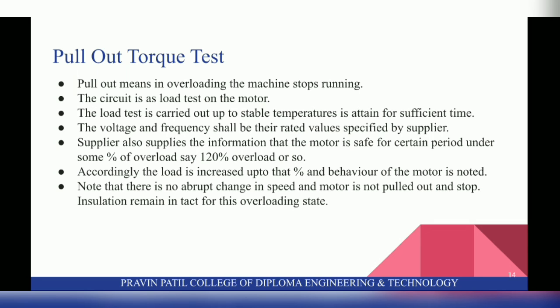Supplier also supplies the information that the motor is safe for certain period under some percent of overload, say 120% overload or so. Accordingly, the load is increased up to that percent and behavior of the motor is noted. Note that there is no abrupt change in speed and motor is not pulled out and stopped. Insulation remains intact for this overloading state.